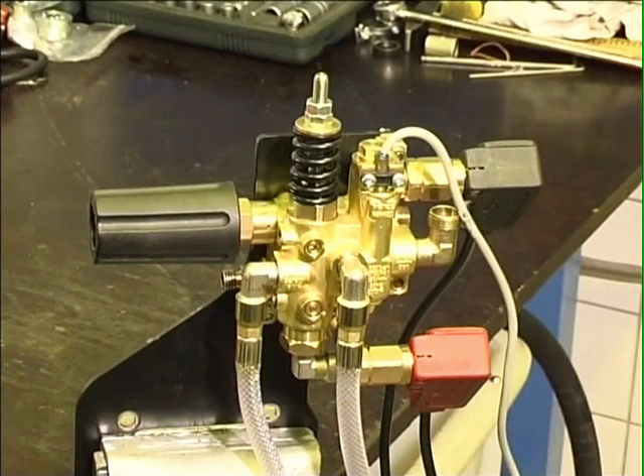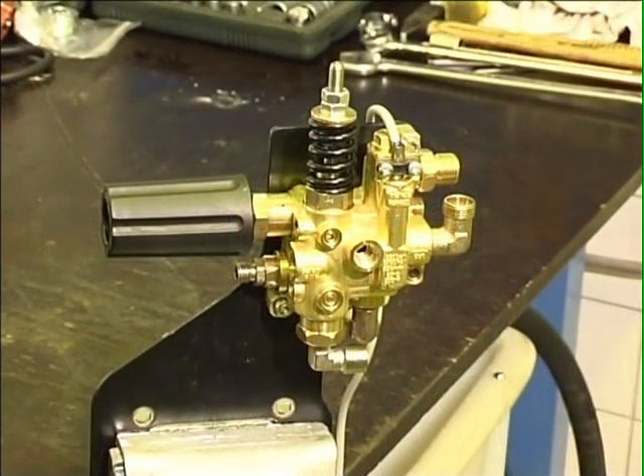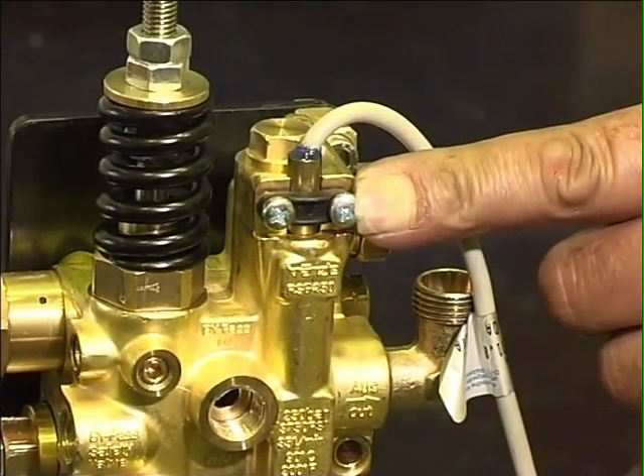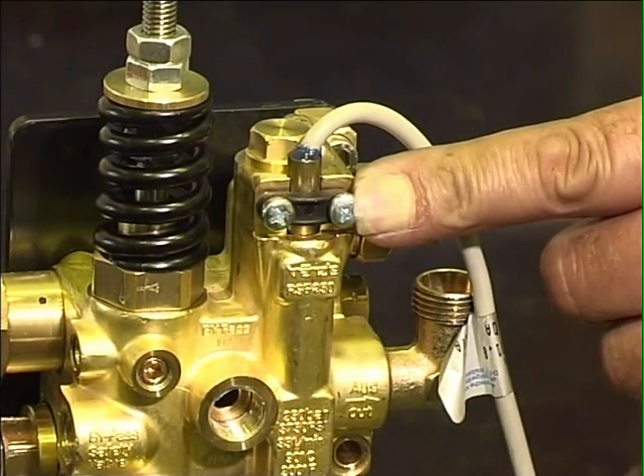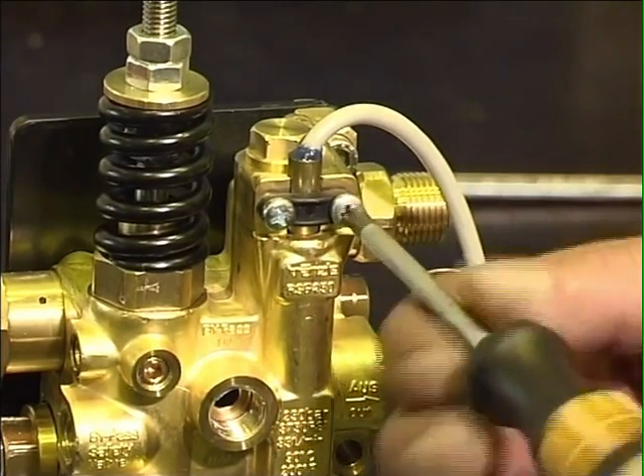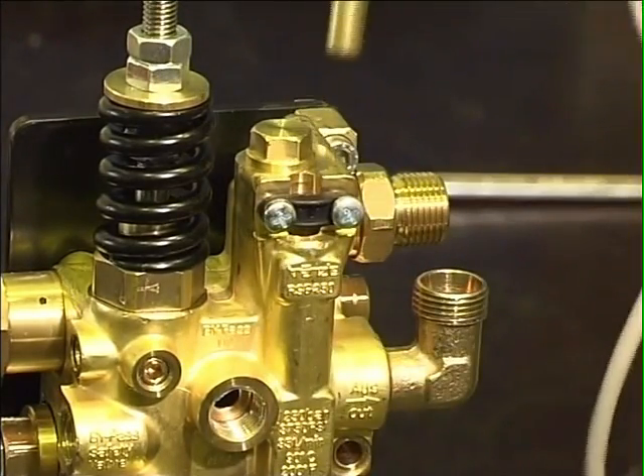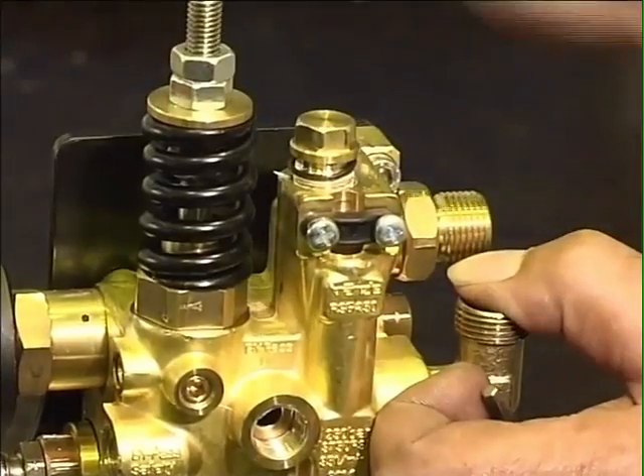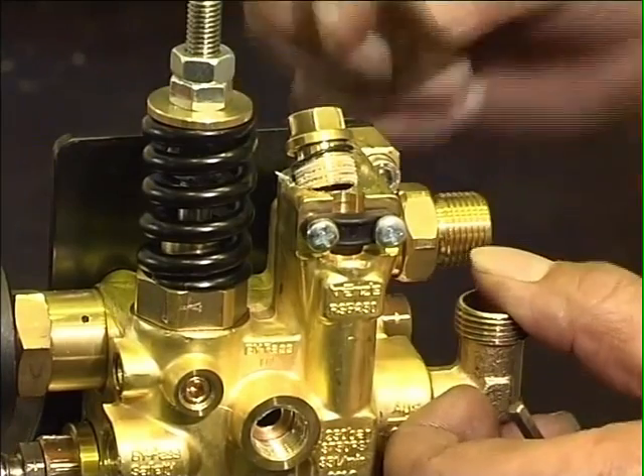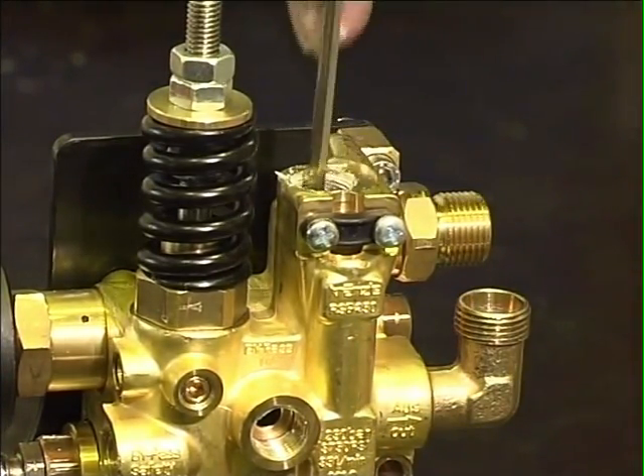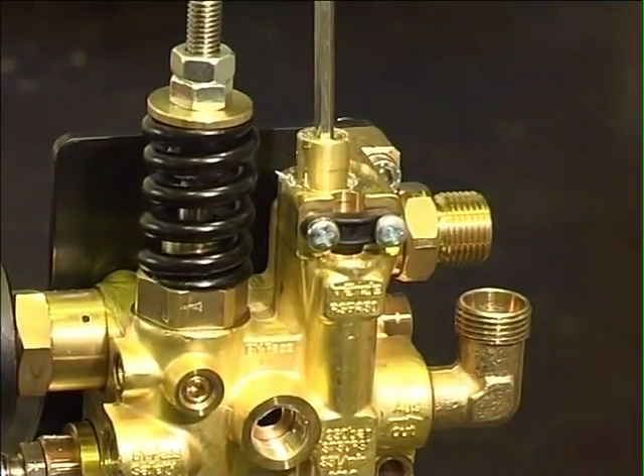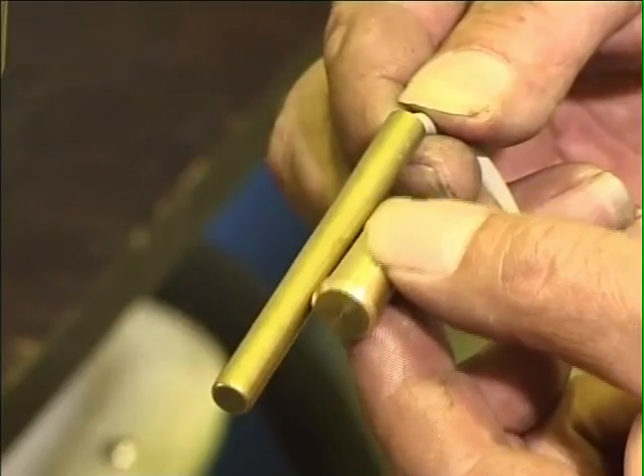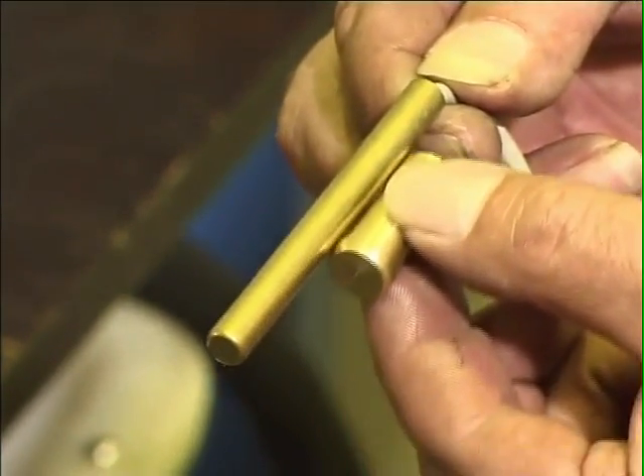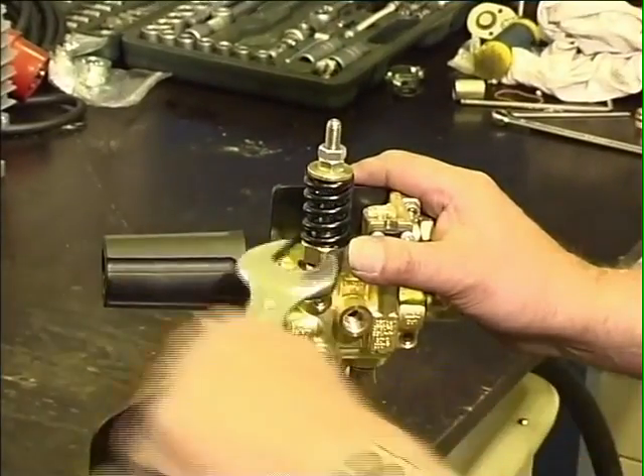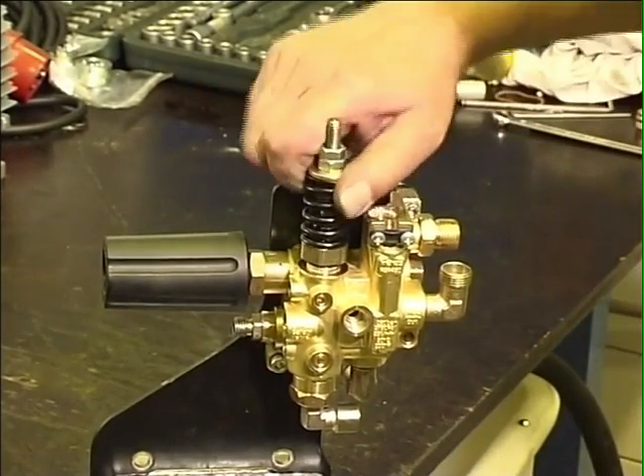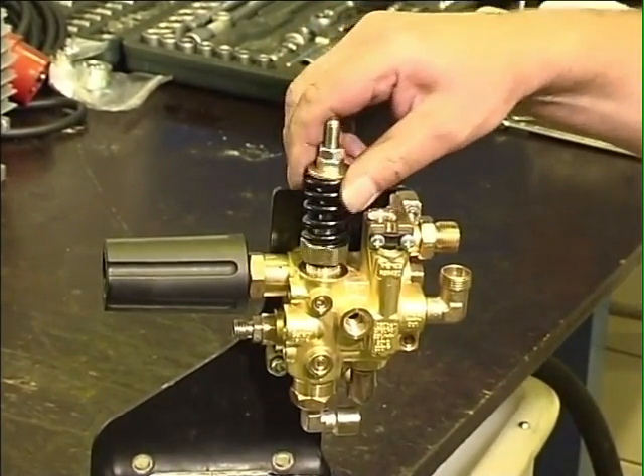For maintenance, first remove the pressure switches and all connections. The flow monitor starts or stops the burner when the gun is closed, that is, no water flows. This is the reed contact of the flow monitor. The floater body contains a magnet that triggers the reed contact of the pressure switch. With a measuring instrument, for example, an ohmmeter, you can check function of magnet and reed contact. The safety valve for the heating coil is located here. Seals must be cleaned or replaced if necessary.